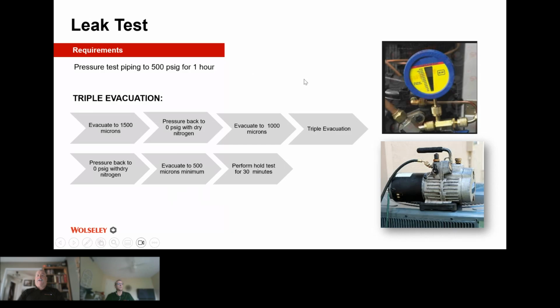Sorry, I missed this one point here at the top. It is important that when you are doing a nitrogen pressure test, you are testing the line set and the joints at 500 psi for an hour. This is a good gauge because working pressure, both in cooling and heating, can get upwards of 425 to 450. So we're going to do 500, because this line set and the joints in the outdoor unit and the indoor unit are rated for over 600 to 800 psi. So 500 is not in any way, shape, or form going to hurt your joints, your service ports, your compression connections, or your line set.